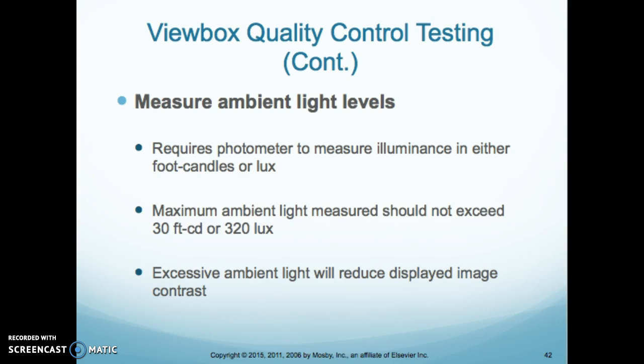Measuring the ambient light levels: you take the photometer and measure the illuminance in either foot candles or lux. The maximum ambient lighting measured should not exceed 30 foot candles or 320 lux. Excessive ambient lighting will reduce displayed image contrast. If the room is too bright where you have the view boxes, you are not going to be able to see your image contrast well. We always dim the lights so that the light coming out of the view box really shows us our contrast.